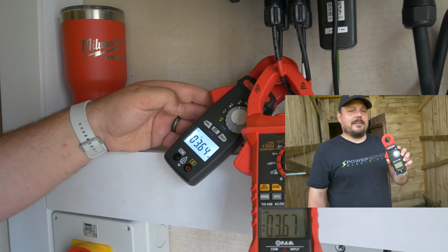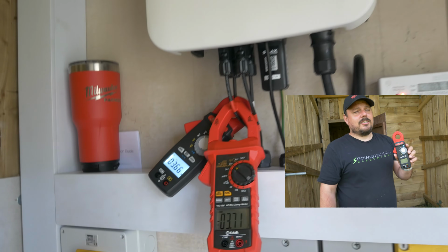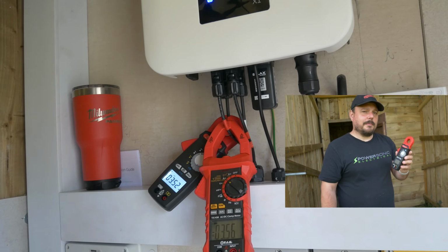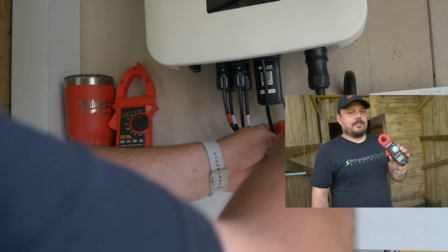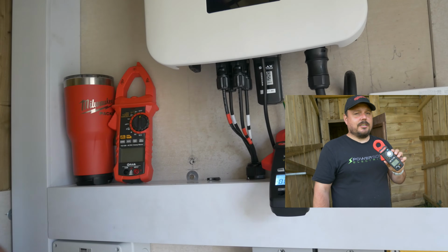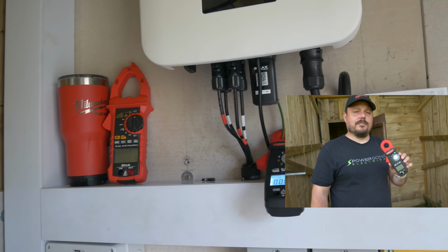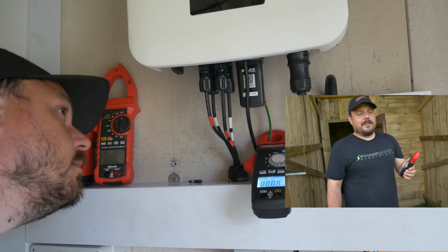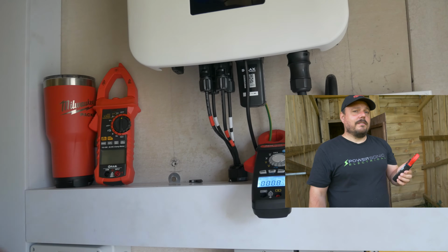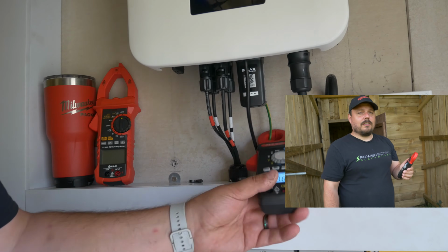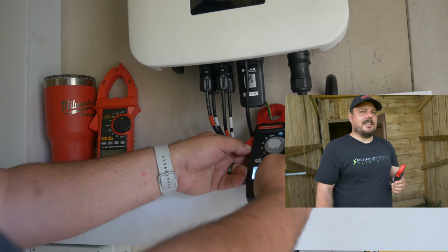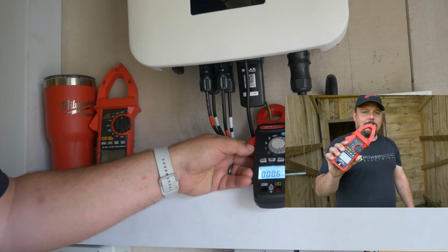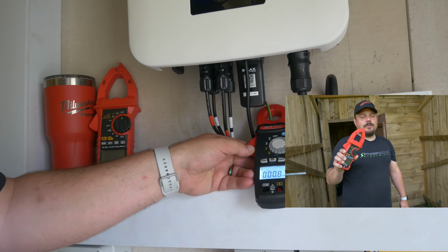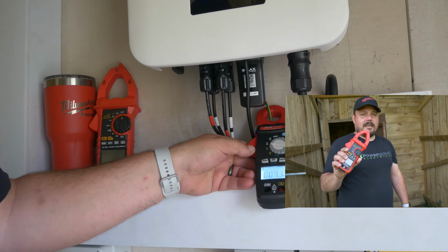These are super handy on DC as well for all of those reasons, so we can measure any current flowing in the PV string cabling, and also use it to see any DC and AC current that might be leaking through the earthing conductor, because for those who've been in PV a while, you'll appreciate a lot of the older inverters actually naturally leak a lot of current to earth, both AC and DC. This clamp meter comes in, I think, the PV200 kit from TIS, alongside an irradiance meter.